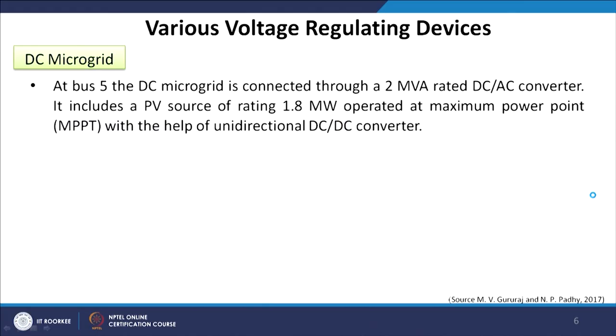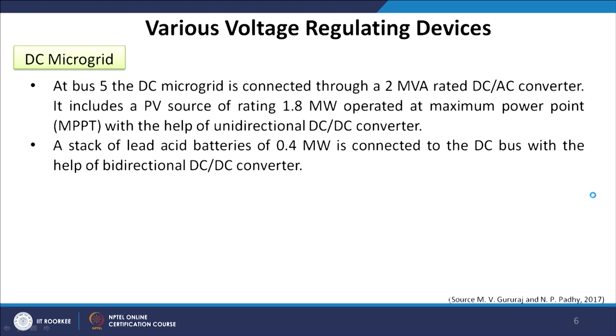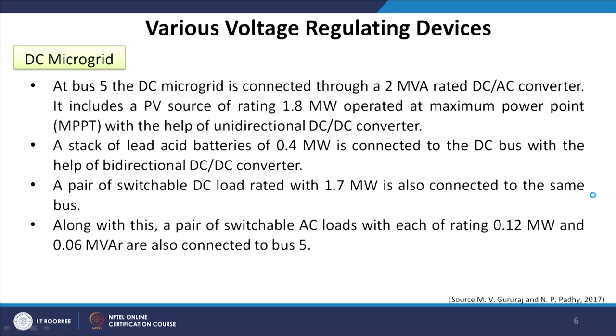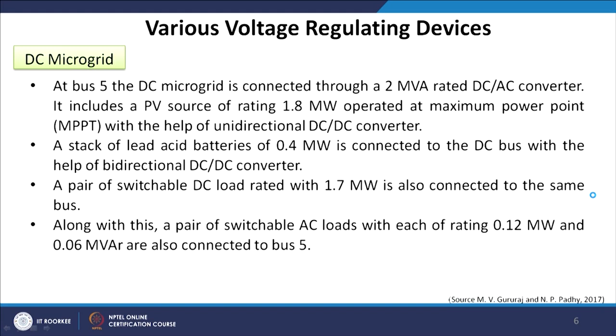A DC microgrid site is included at bus number 5, where it is connected through a 2 MVA rated DC-AC converter. It includes a PV source of rating 1.8 MW operated at MPPT using a unidirectional DC-DC converter. A stack of lead-acid batteries with capacity 0.4 MW is also connected at the same bus, along with a pair of switchable DC loads rated at 1.7 MW and a pair of switchable AC loads each rated at 0.12 MW and 0.06 MVAr.